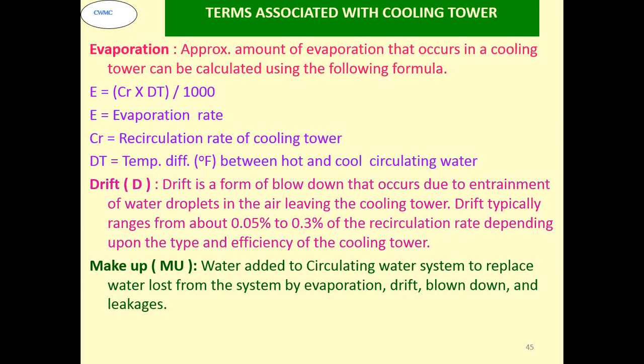As we said, evaporation. Evaporation is equal to the circulation rate multiplied by the differential temperature divided by 1000, where E is the evaporation rate, C is the circulation rate, and dT is the differential temperature between hot and cool circulating water. Drift is a form of blowdown that occurs due to entrainment of water droplets in the air leaving the cooling tower. Drift typically ranges from about 0.05% to 0.3%, but today, as I said, efficient drift eliminators are there and you can comfortably achieve 0.0005% of the circulation rate.